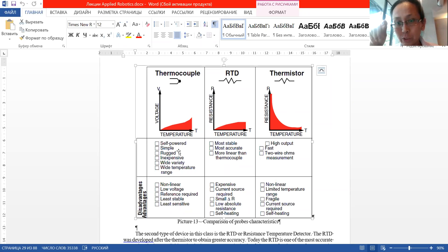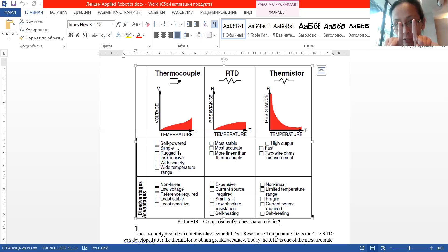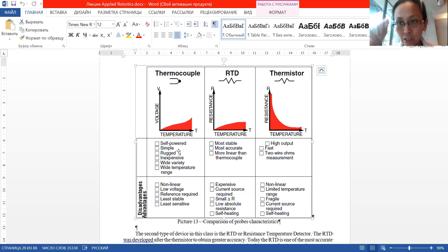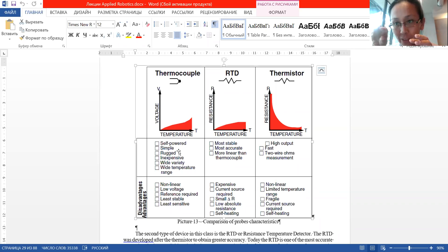The advantage of thermistors is that they have very high resistance, so you can easily measure it because the difference is large. They are very fast and you can measure resistance at two points as shown in the circuit diagram. The disadvantages are nonlinearity, limited temperature range, fragility — they can break easily — they require power supply, and like RTDs, they self-heat and can introduce measurement errors.